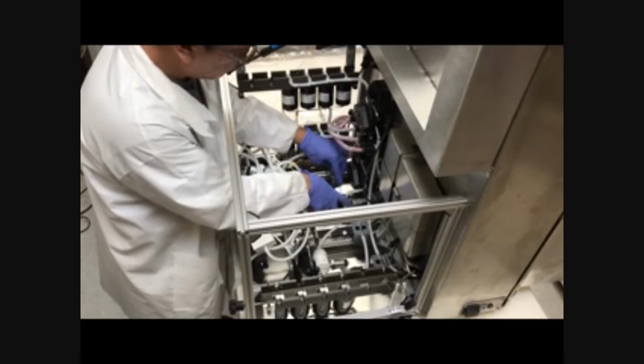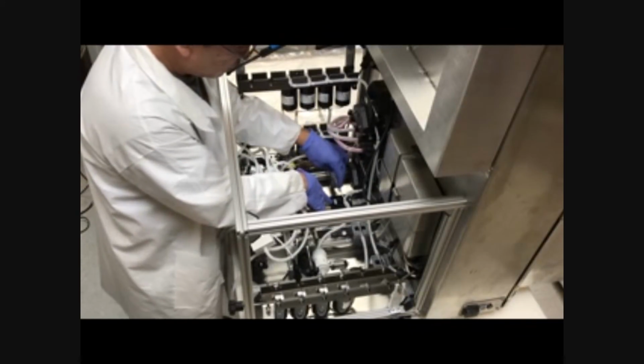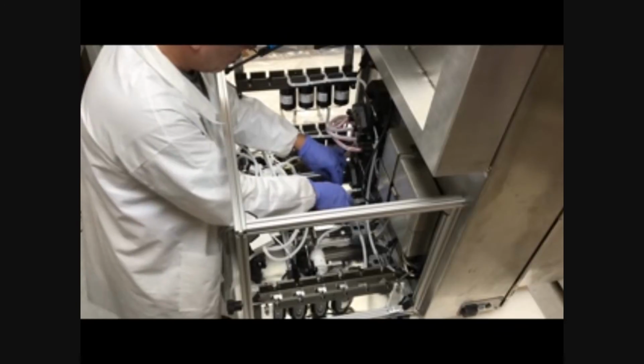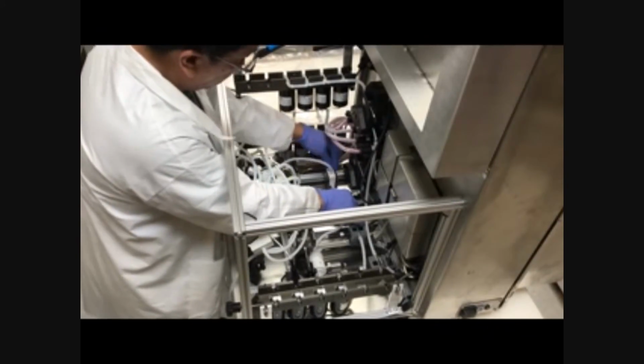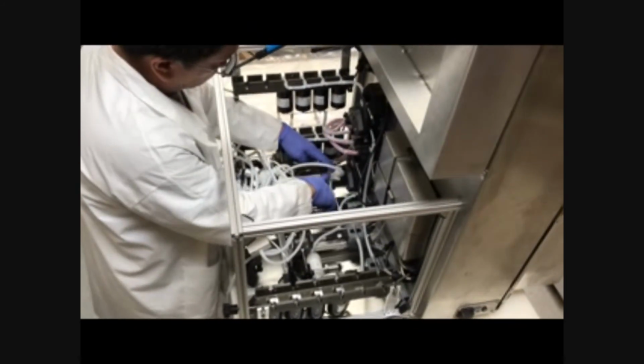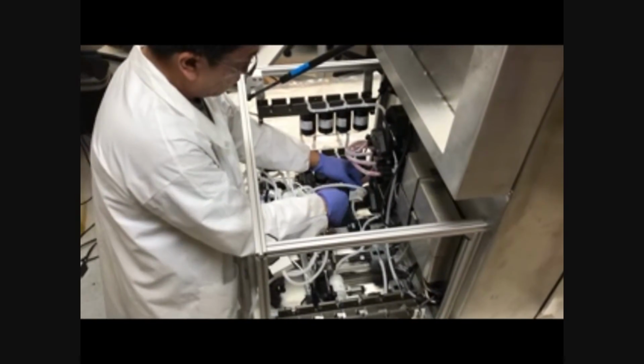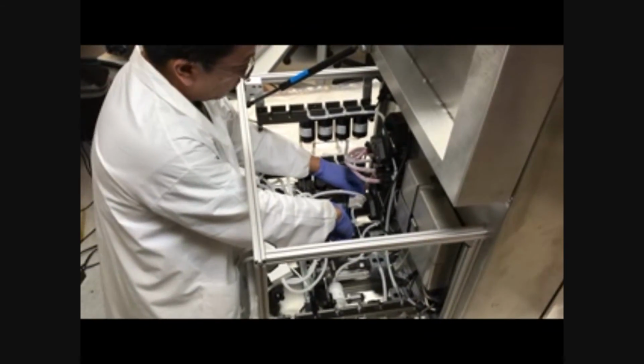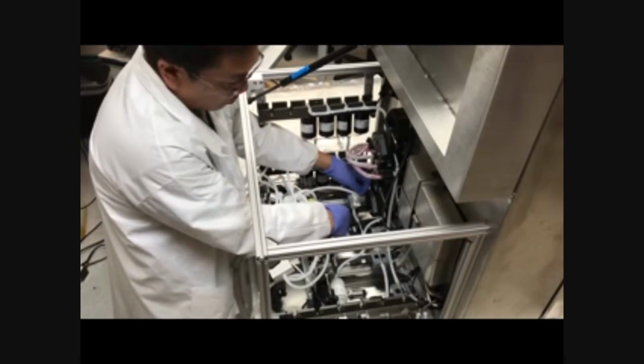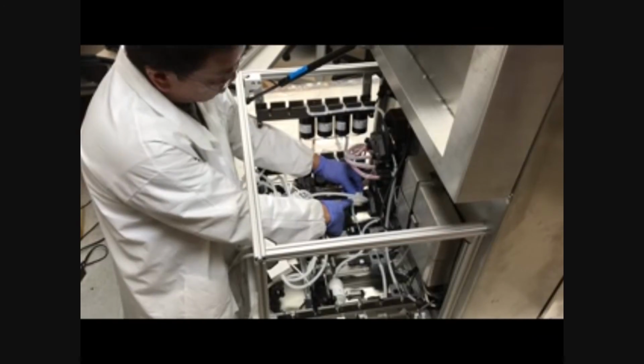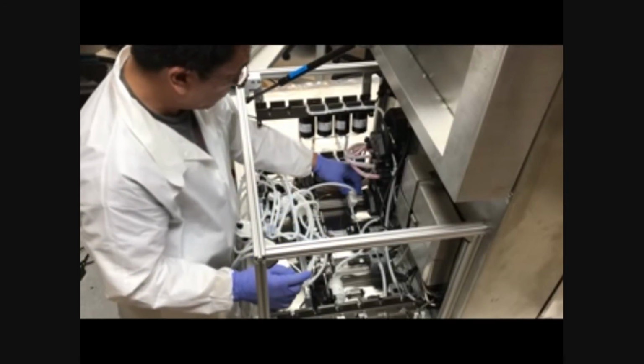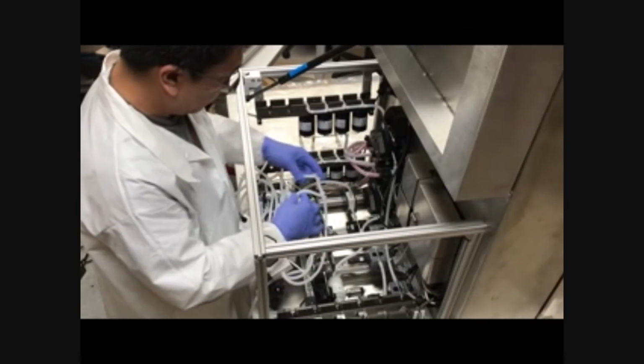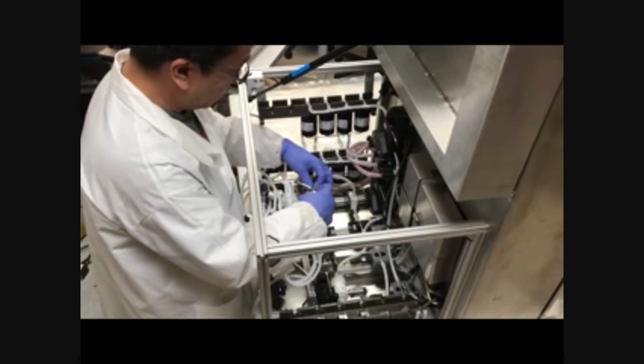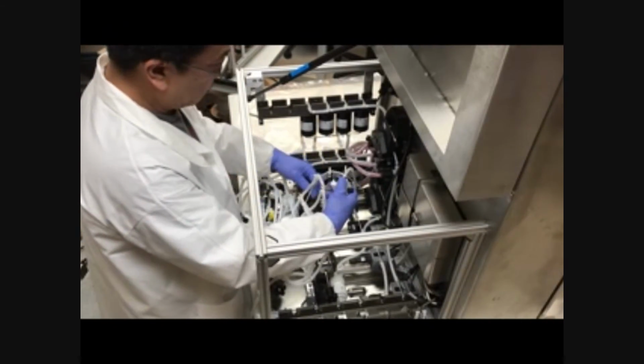And the next step is to install the pH sensor, the conductivity sensor, and the air sensor. So he's threading the tube. He just pushes the tube into the air sensor and is doing the installation. Danny, is that the pH or the conductivity sensor? pH1. That's the pH1, that's the pre-column pH sensor. So he just put that in the slot.